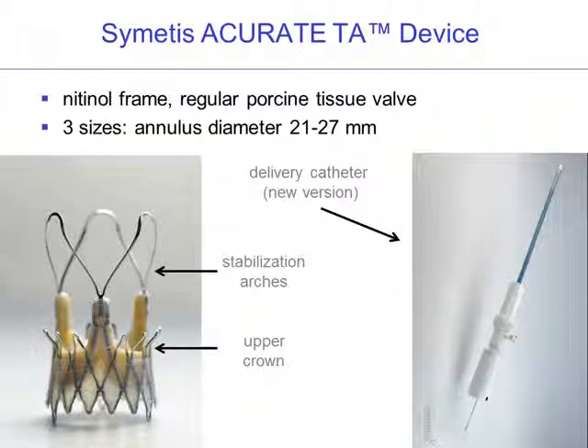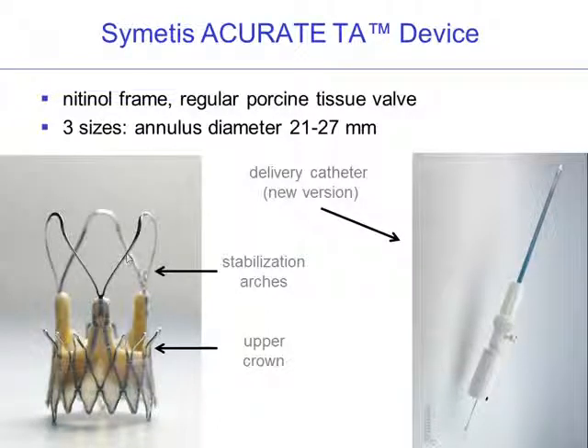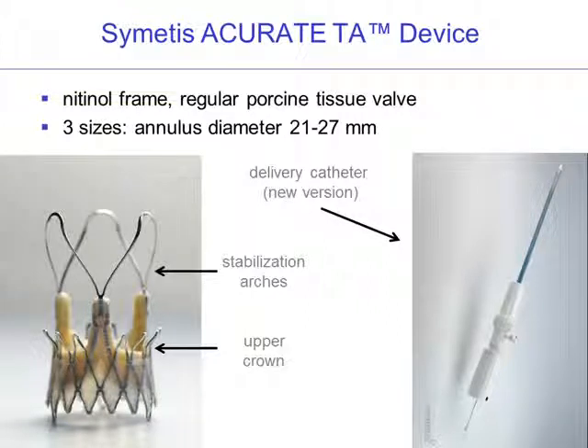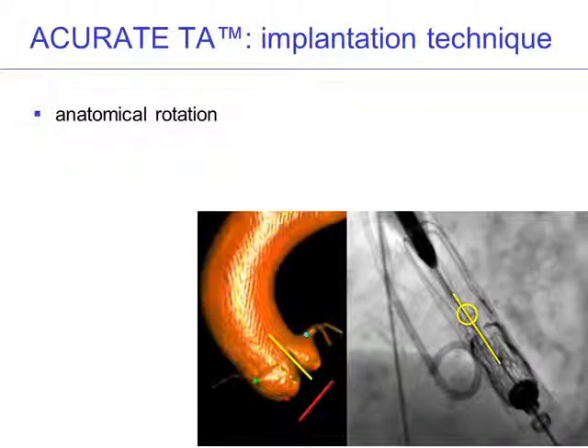On the left, you can see the Nitinol stent. It has two specific features important for implantation. First are the stabilization arches, which are meant to prevent tilting of the valve during deployment. The other key feature is the so-called upper crown — the most distal part of the stent body — which is partially unsheathed during step one of deployment and then provides tactile feedback during actual implantation.